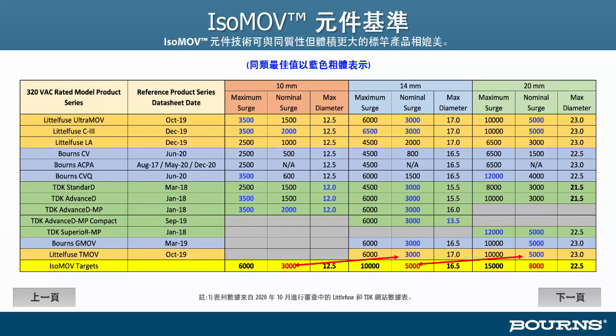Well, we looked at many competitor data sheets as well as data sheets for Bourns MOV products. We focused on the 320-volt AC-rated products, and we looked at 10mm, 14mm, and 20mm products. We compared the nominal surge rating and the maximum product diameter from the datasheets. Notice that the maximum product diameter from the datasheet doesn't really correspond particularly well to the nominal size designation. However, it does give you an idea of the class size of products offered. Another thing to notice is that for a market that many believe is highly commoditized, there's really quite a bit of variation in the ratings of the various product lines. The best-in-class rating for each size is highlighted in blue.